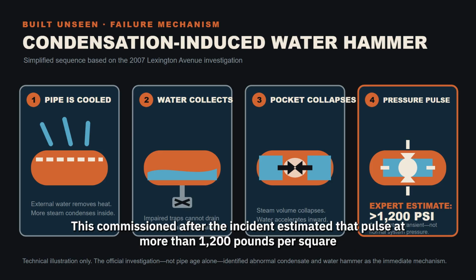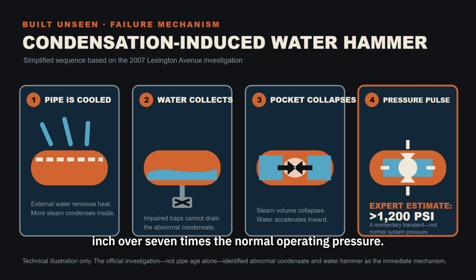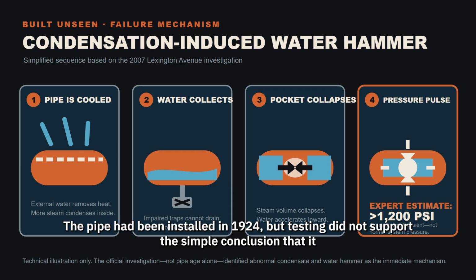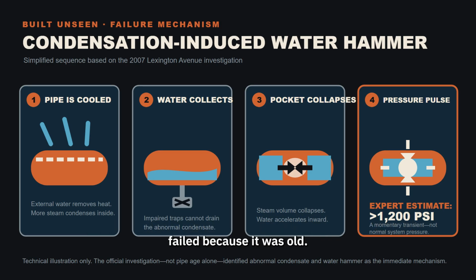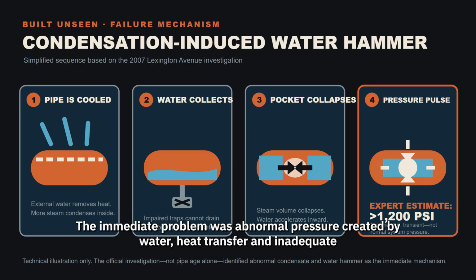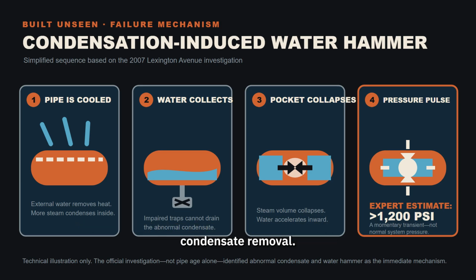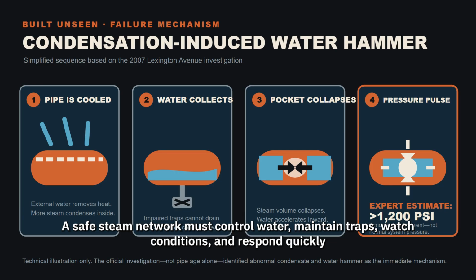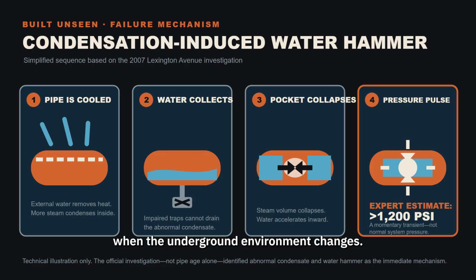Reports commissioned after the incident estimated that pulse at more than 1,200 pounds per square inch, over 7 times the normal operating pressure. The pipe had been installed in 1924, but testing did not support the simple conclusion that it failed because it was old. The immediate problem was abnormal pressure created by water, heat transfer, and inadequate condensate removal. That distinction matters. Replacing every old pipe would not remove the physics. A safe steam network must control water, maintain traps, watch conditions, and respond quickly when the underground environment changes.